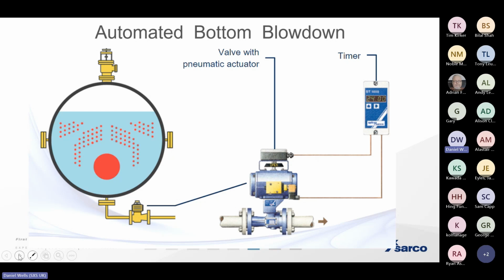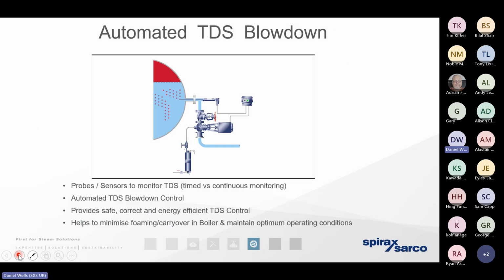Unfortunately, with bottom blowdown, there's no opportunity for heat recovery. It's got to go straight to the bottom blowdown vessel with no hindrance there. But what we could perhaps look at doing is moving away from a manual blowdown valve to an automated bottom blowdown valve. If we've got a timer on the actuator, then by understanding the size of the valve, the pressure of the boiler, and the number of seconds it's in the fully open position, we're able to have a good understanding of the mass of hot water that's being flushed to waste, and therefore the efficiency versus inefficiency. All we can really hope for is to keep that mass of hot water that's dumped to waste to an absolute minimum. And then we spoke about the TDS blowdown, remembering that TDS stands for total dissolved solids.